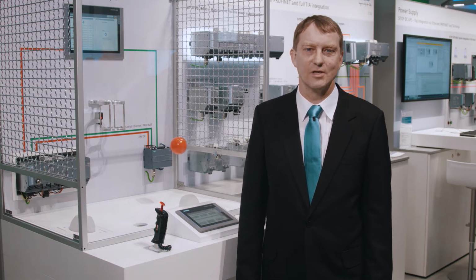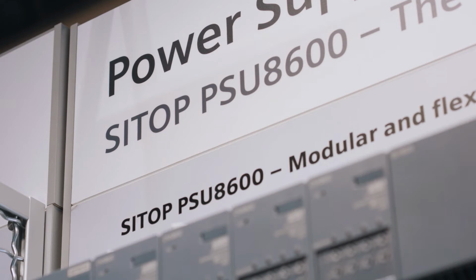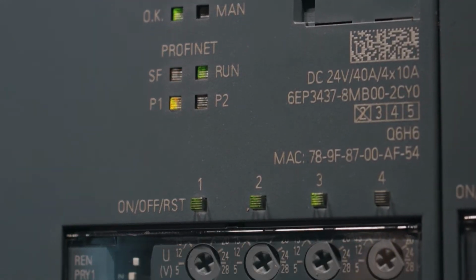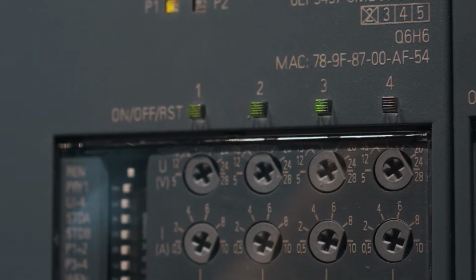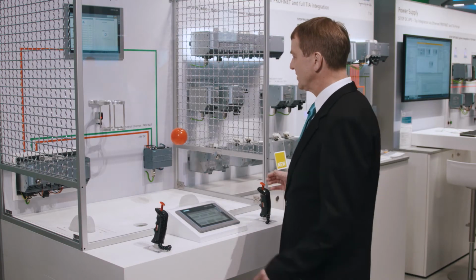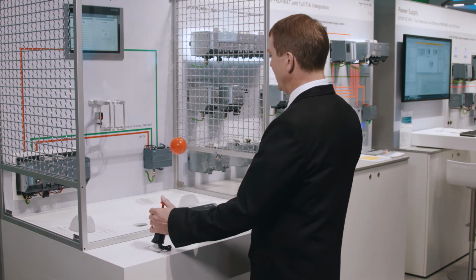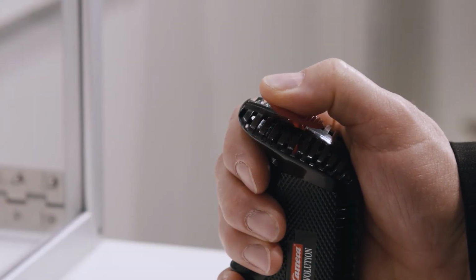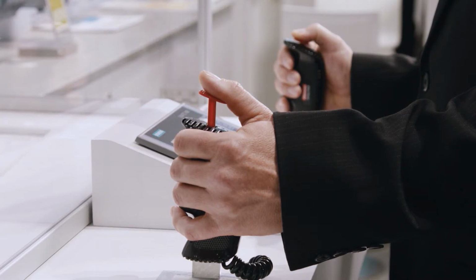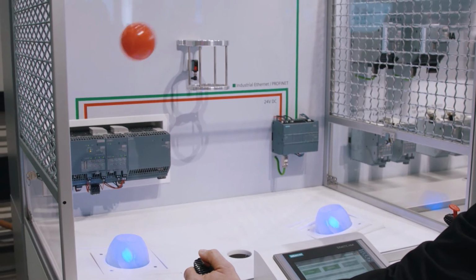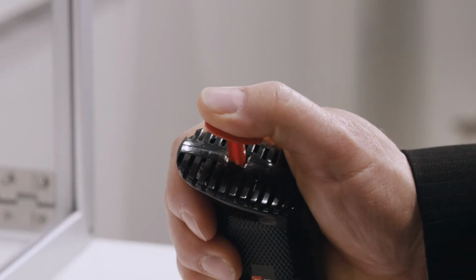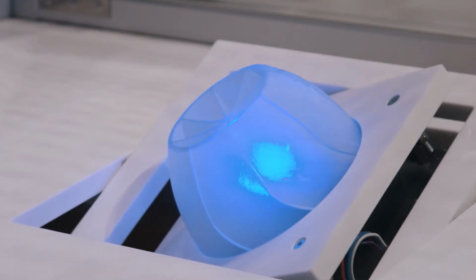I would like to show you several opportunities of the unique SITOP PSU8600 power supply system using this model. It has multiple outputs whose voltage and power can be set individually. The output voltage can be changed between 5 and 28 volts, even dynamically, due to the variable voltage supply of the ventilators in this model. Its speed, the power of the airflow, and thus the altitude of the ball are changing. If the ventilator is panned, in addition, the ball can even be juggled.